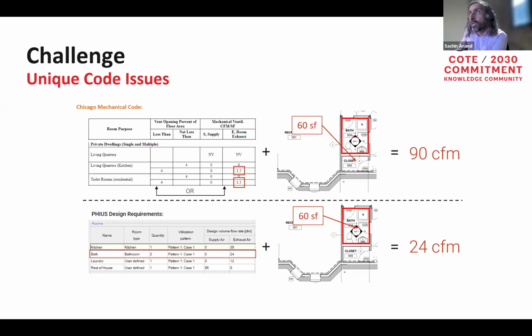And this is where we had to go to a much higher efficiency energy recovery. So the exhaust is coming through the energy recovery, and I think our energy recovery system, which is coming up on one of the slides, is close to 80 to 85% effectiveness, which comes at a premium. That darn little energy recovery system from Zehnder was like $5,000 or $6,000 - top of the line, but also top of the line from a cost perspective.